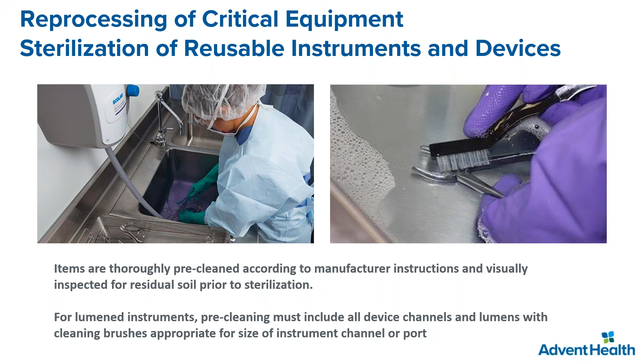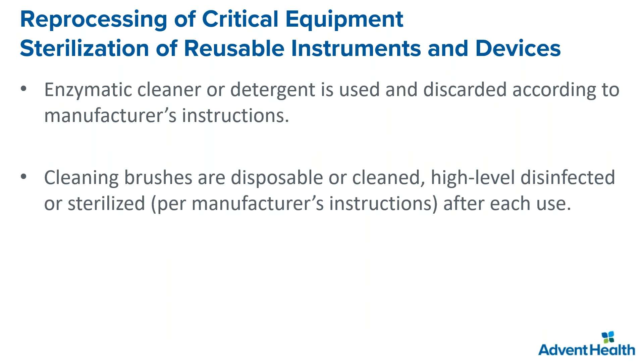Also, in the reprocessing of critical equipment, we use enzymatic cleaners, and those enzymes are digesting whatever is left in that instrument. And this detergent is used and discarded according to the manufacturer instructions. Also, cleaning brushes are disposable or cleaned, high-level disinfected, or sterilized per manufacturer instructions after each use. Always remember that you have to follow your manufacturer instructions every time.